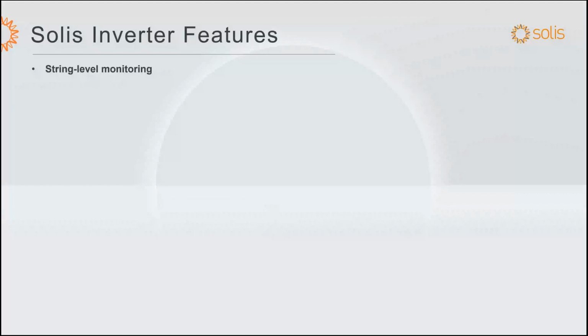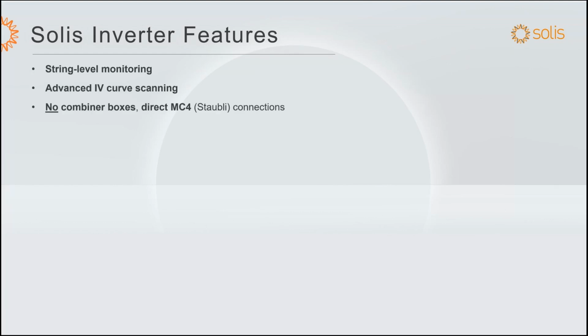So now we'll talk about the inverter features that are common to all of our three-phase inverters, and we'll start with string level monitoring. So you have string level monitoring capability on every single inverter from 25 kilowatt to 350. We also have advanced IV curve scanning. So if you want to do IV curve scanning remotely, you can do that with our inverters. No combiner boxes. Combiner boxes can potentially be a failure point. All of our connections are directly into the inverters with MC4 Stäubli.